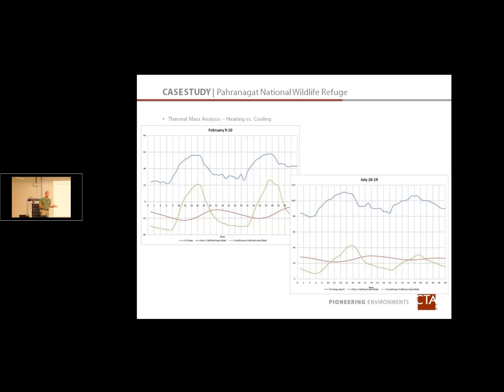So right away when we had that box, I could start looking at different ideas that we were throwing around, passive strategies. And this one is mass. To break it down, the blue here is the outside air temperature, in both cases. This is February, which happened to be the peak heating day, and this one is July, which happened to be the peak cooling day. The green here is a code-compliant frame wall, I think we were stick frame here, and the red one is thermal mass, about 8 inches of concrete, so a significant amount.